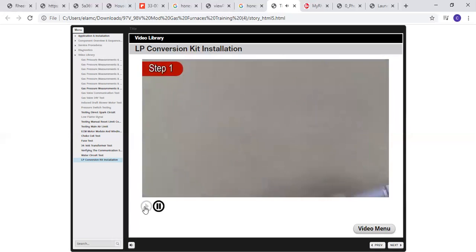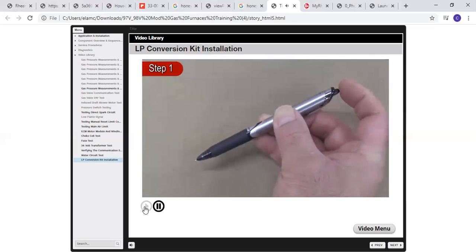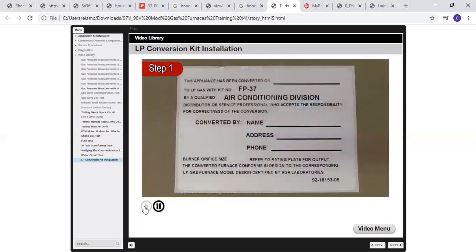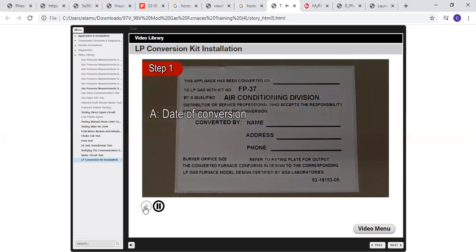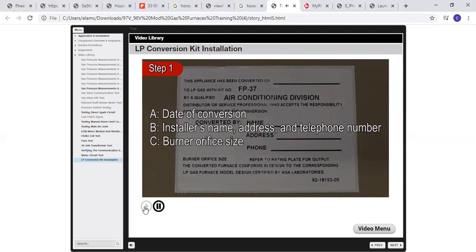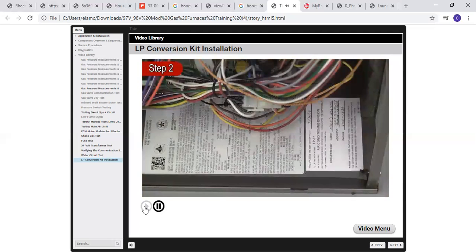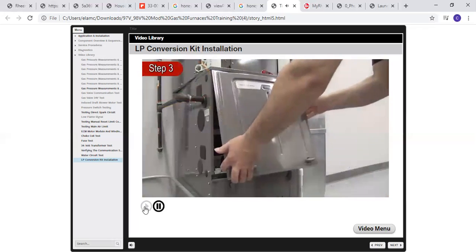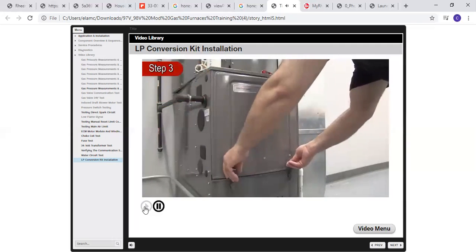Completing conversion. Step 1. Using a ballpoint indelible pen, record the following information on label 92-18153-05 provided in this kit. A. Date of conversion. B. Installer's name, address, and telephone number. C. Burner orifice size. Step 2. Place completed conversion label next to the rating plate. Step 3. Install the burner compartment access door.